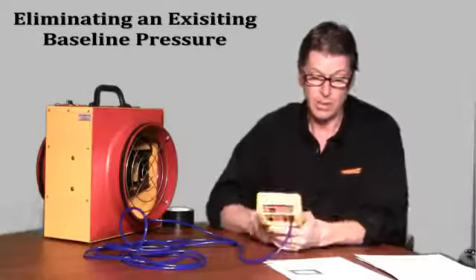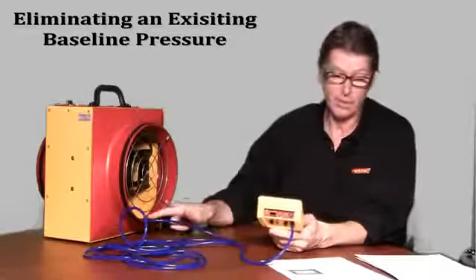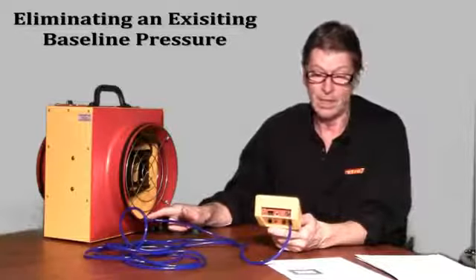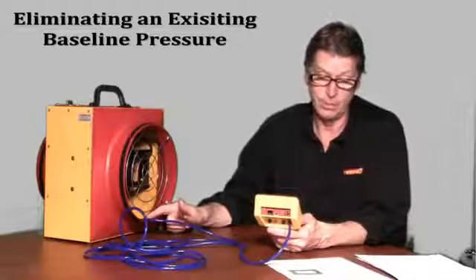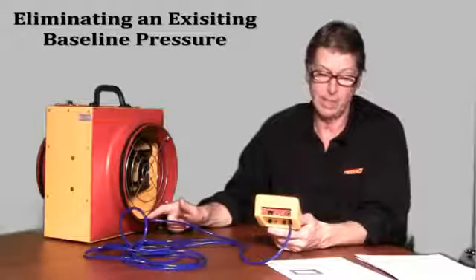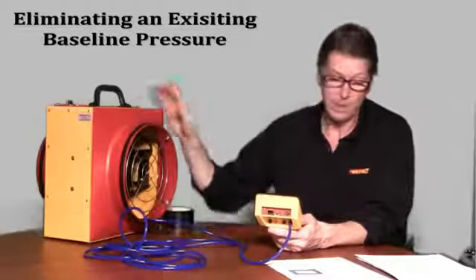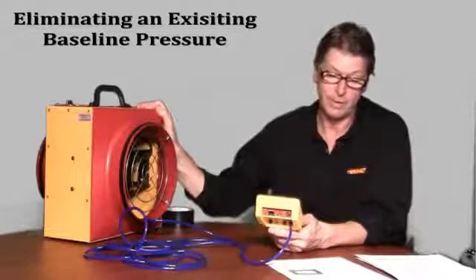Step one of the procedure is to tape the other end of the tube inside a fan exhaust, simulating wind blowing on the tube. This will create a baseline pressure. Adjust the speed of the fan until we have roughly 25 Pa.